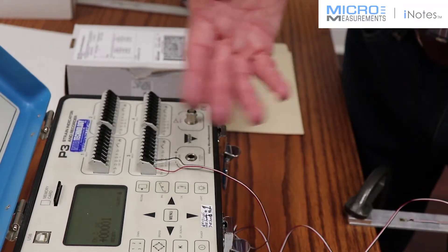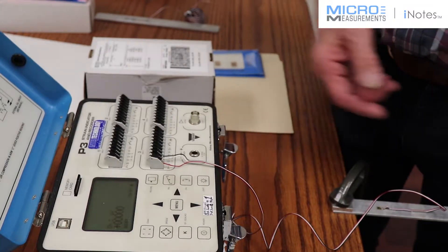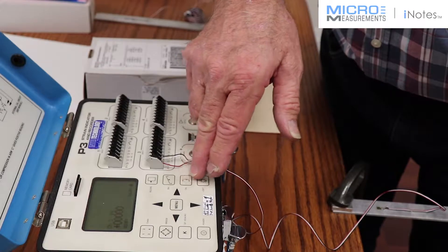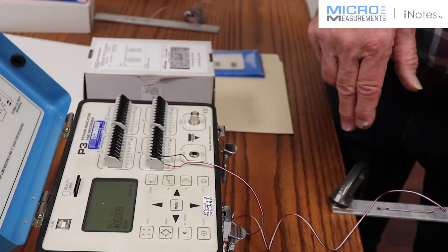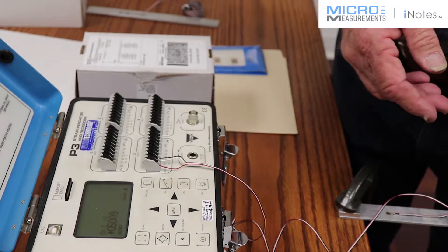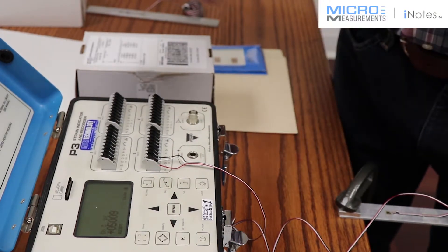We have the ability to check calibration before we start to take readings or record readings. So if I press the cal button, it should be giving me a 5000 micro strain readout for the gauge factor of two.